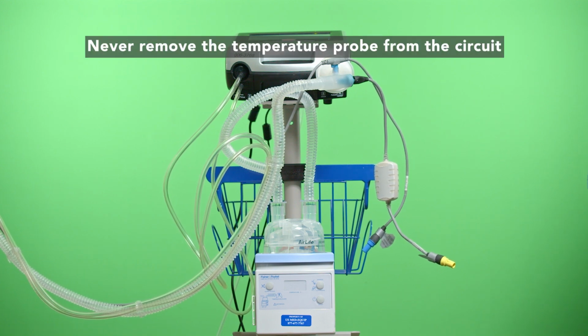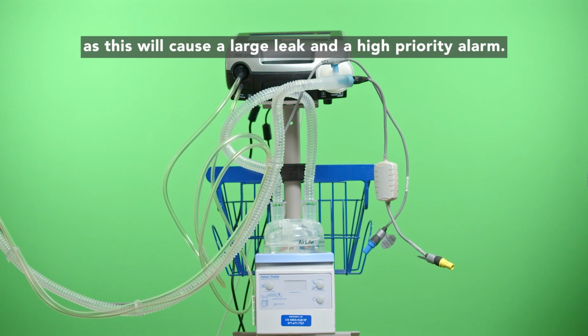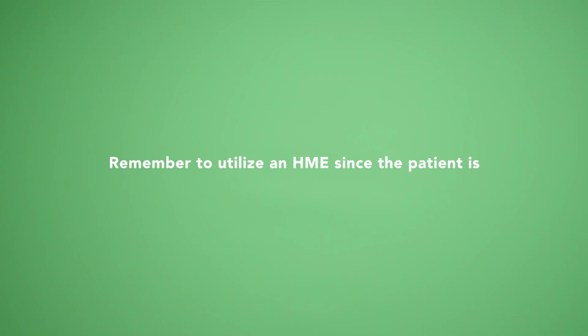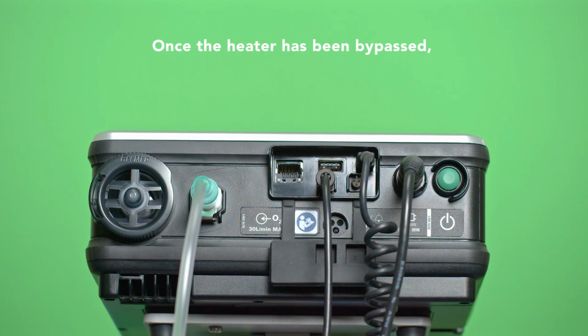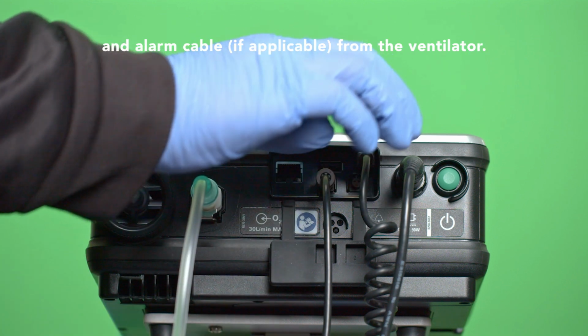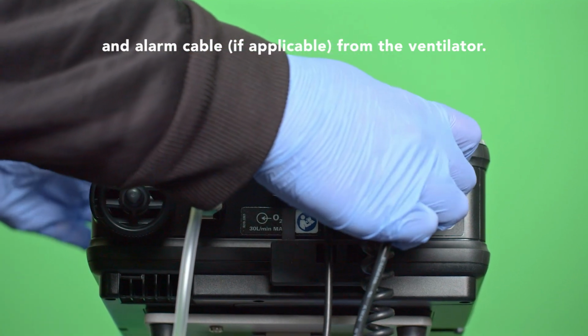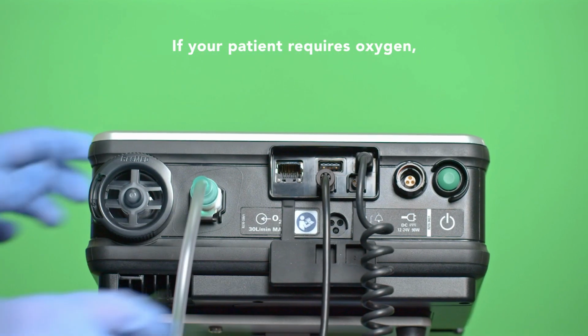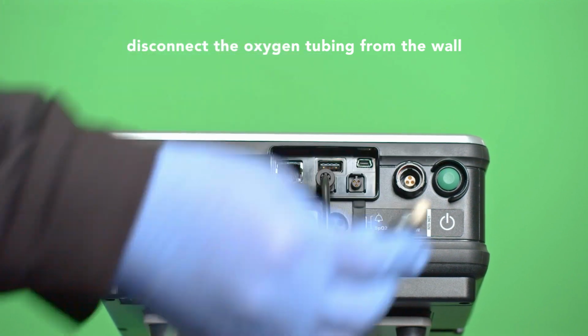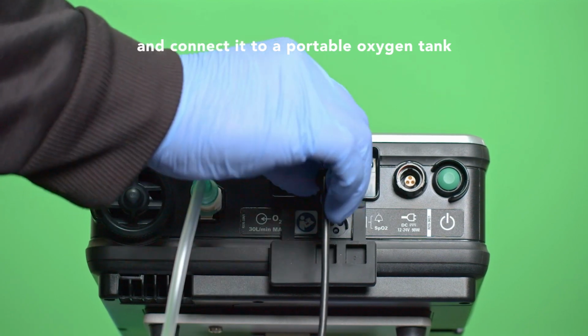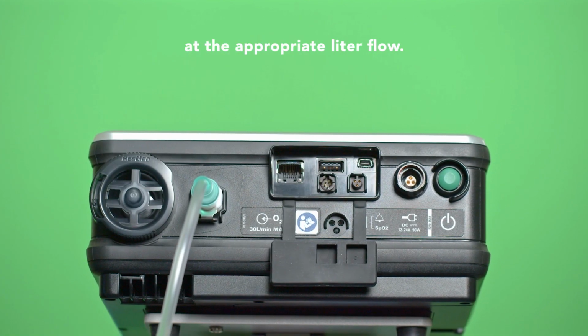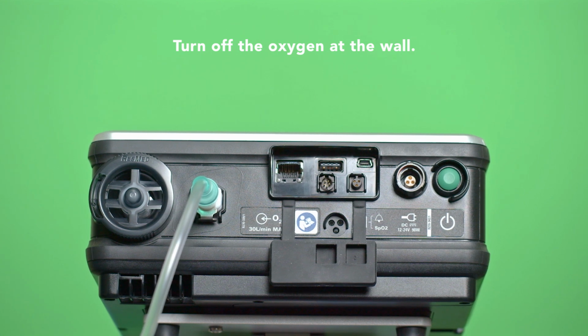Never remove the temperature probes from the circuit, as this will cause a large leak and a high priority alarm. Remember to utilize an HME since the patient is no longer receiving humidification from the heater. Once the heater has been bypassed, you will need to disconnect the power cord, micro USB, and alarm cable, if applicable, from the ventilator. If your patient requires oxygen, disconnect the oxygen tubing from the wall and connect it to a portable oxygen tank at the appropriate liter flow. Turn off the oxygen at the wall.